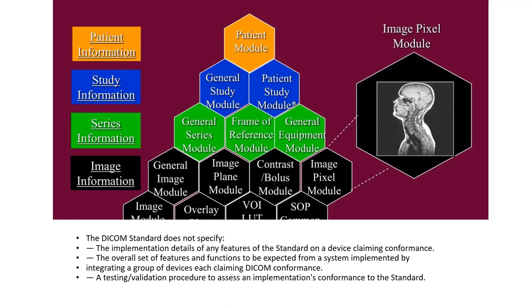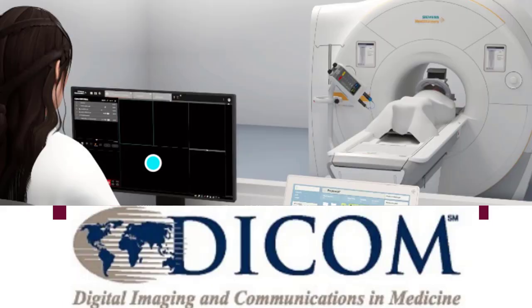Let's look at what the DICOM standard does not specify. It does not specify the implementation details of any features of the standard on a device claiming conformance — it only indicates that the different modalities will act interoperably. It also does not specify the overall set of features and functions expected from a system integrating devices each claiming DICOM conformance, nor is it a test or validation procedure. It simply states that equipment is capable of interfacing with other equipment that also has a DICOM base.